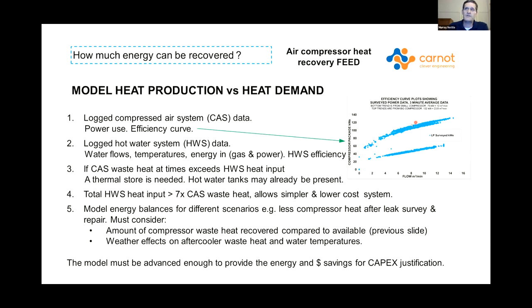So if you had done a survey and you're modeling your heat recovery based on the bigger compressor, then all of a sudden you actually started being more efficient and ran the smaller compressor most of the time, the amount of energy you've got available for your heat recovery system has gone down quite a lot, and your economics might go out the window. Similarly, if you decide to do leak repairs, you might move from operating here to operating here. Now, these are fixed speed machines. If you've got a variable speed machine, it might actually be going somewhere down like this. So the model needs to be advanced enough to be able to provide the energy savings for the CapEx justification to take you forward.